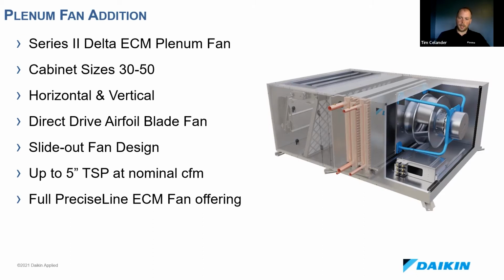And the other thing I'd like to highlight, you can kind of see it here with this shadow view, the rail that it's mounted on allows for slide out access. So if you're ever doing any maintenance or replacing the fan, you just unplug the electrical connections and you can pull it out with the blue frame that you see there. So with the plenum fan additions, we have an EC fan or ECM fan offering throughout the whole PreciseLine product line.